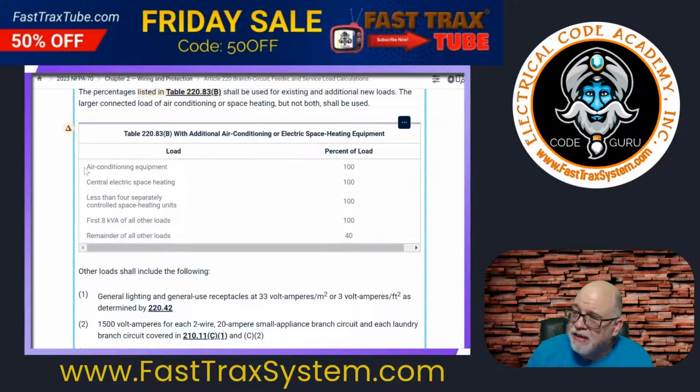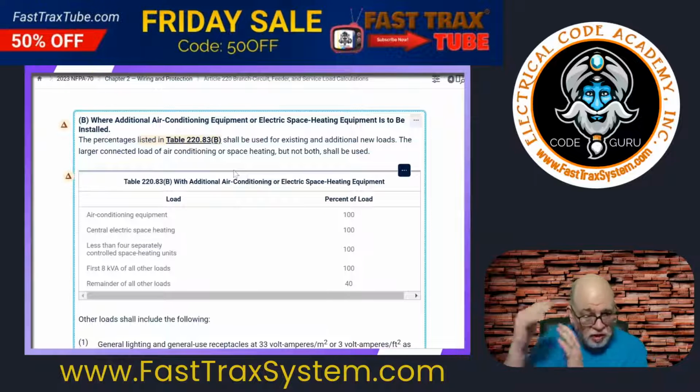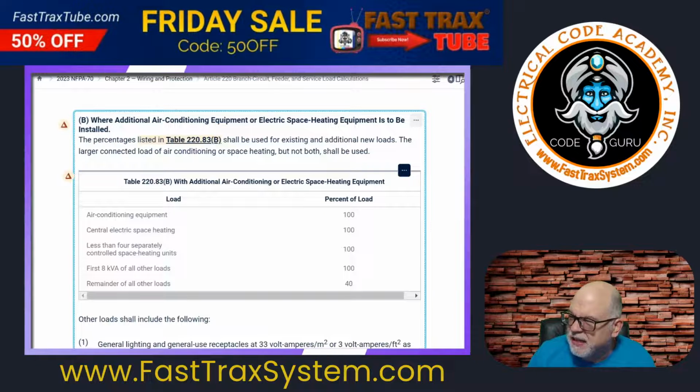But now if you have additional air conditioning equipment, you take it at 100%, or you have central electric space heating, you take it at 100%. Or if you have less than 4 separately controlled space heating units, you take them at 100%. So what that means is you're taking the additional air conditioning or heating or the separately controlled space heating all at 100%. But you're only taking the larger of those, okay? So that's what it tells you up here, right? It says the larger connected load of air conditioning or space heating, but not both, shall be used.